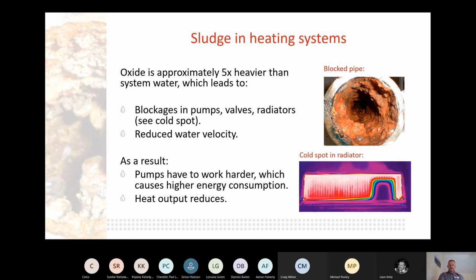Oxide is approximately 5 times heavier than system water. So if you say sludge, which leads to blockages, as it says there, you've got the image on the top right. The one we're probably more common with in the domestic setting would be a cold spot in a radiator, where it's got to work harder to get sufficient heat out. That will also result in reduced outputs. That's just an infrared camera showing the sludge build-up where the waterway's got to push over that.